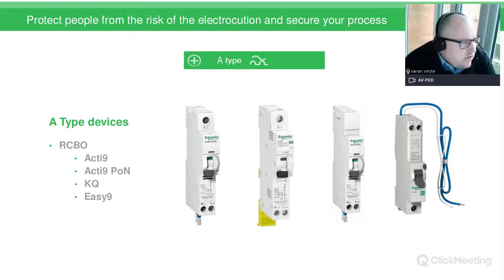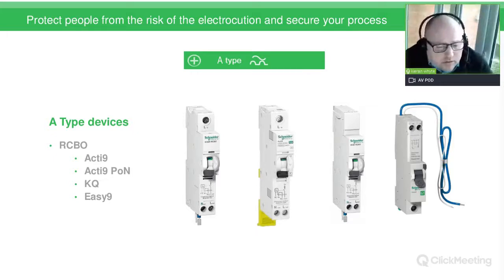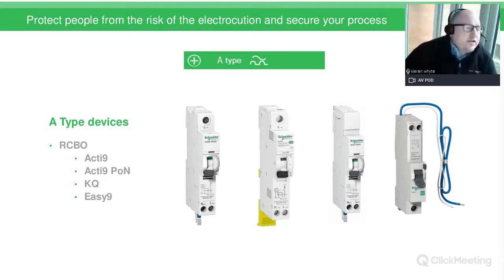So within the Schneider range, we have the A-type RCBOs, within our Acti9 range, our plug-on neutral range, our KQ, and our Easy9 range. As a standard, because we see the industry moving, and with pretty much all loads on systems these days having some influence of a DC circuit, unless it's a specific load, we're looking at A-type RCBOs, 30 milliamp, for your RCB selection. 30 milliamp is the most commonly used in the industry. It means that when the threshold of 30 milliamps of earth leakage is reached, the system will trip.